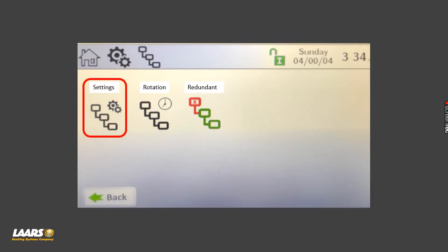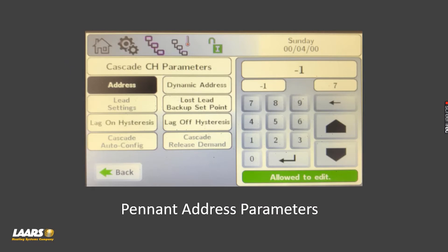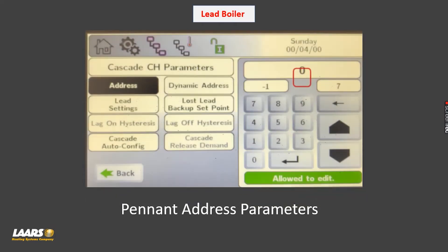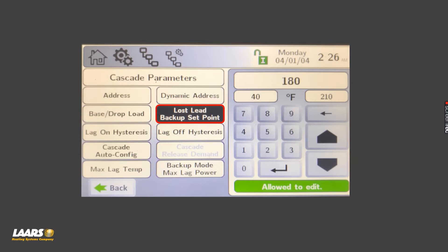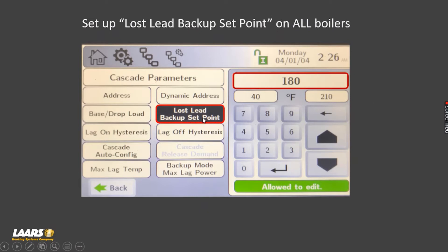We'll also talk about settings — this is the Pennant addressing. On the Pennant, the range is minus one to seven. Minus one means it's unconfigured for a cascading bank, so each boiler leaves the factory defaulted as minus one. The lead boiler gets an address of zero; your member boilers get addresses from one to seven. On your leader, you also want to click on the backup setpoint box and give that a value — in this example 180 degrees — so if the leader gets shut off, your member boilers will come on.